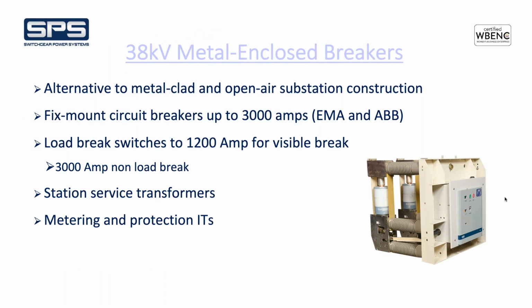So we believe that 38 kV switchgear utilizing circuit breakers, fixed mount in particular, is a good alternative to both metal clad switchgear and open air substation construction. So we utilize a fixed mounted circuit breaker up to 3000 amps. We utilize an EMA breaker, which is what is pictured here. And we also offer an ABB circuit breaker option.